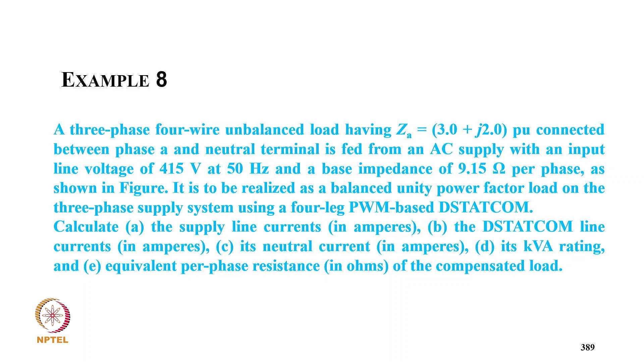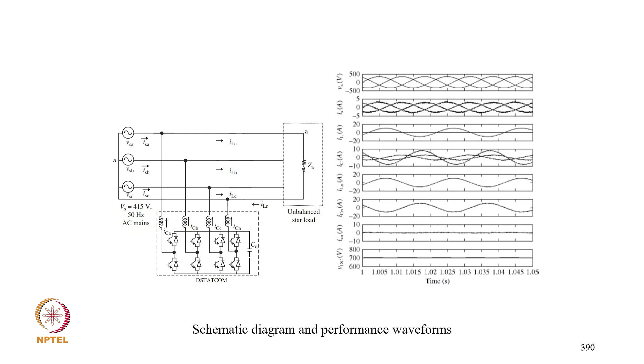Calculate the supply line current, the DSTATCOM line current, its neutral current, its kVA rating, and the equivalent per phase resistance of the compensated load. So this is the typical case where you have a single phase load connected line to neutral, and we have a 4-leg VSC for compensation. We get unity power factor and all the parameters in the waveform.